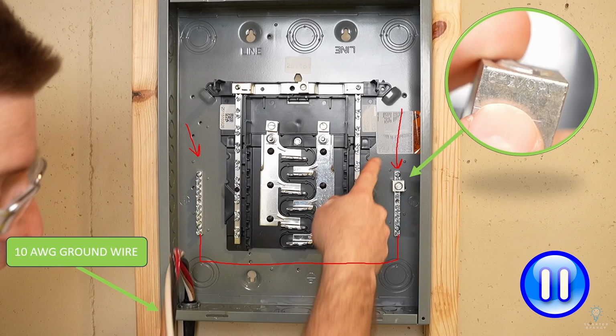The only real issue here is we can't use that lug because that lug is too big for my case here. Now, if you were actually running this as a 100 amp sub panel, chances are you would be using 4-gauge aluminum SER wire, which would come with a 6-gauge ground wire. Well, that 6-gauge ground wire is going to be too big for these little screw terminals here.